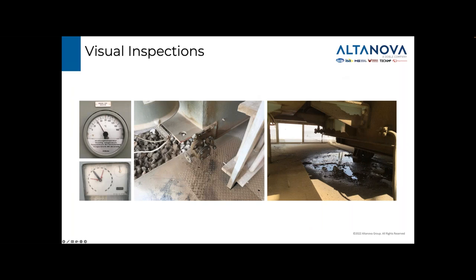Visual inspections are really helpful. They can help identify root causes in the oil data that we get back from the lab. You should check the transformer's physical condition, take note if there are any leaks, and check the tap changer position along with the recording, the drag hands and number of taps. Note the winding temperature indicator settings, the condition of the radiators, pumps and fans, and note any vegetation growth within the transformer bund which may interfere with the cooling of the asset. It's also a good time to use other devices like corona cams, thermal imaging equipment, and PD services as corroborating evidence.